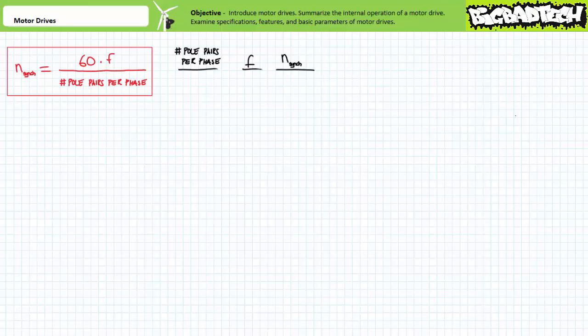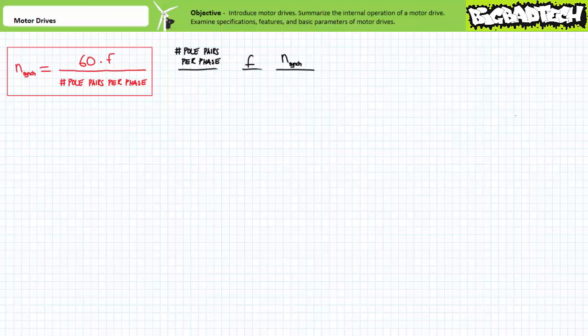Regardless of the terminology employed, all of these devices are solid-state power electronics devices that vary or adjust the magnitude and frequency of applied voltage to a motor under their direction. Returning to those qualities that affect synchronous speed — notably frequency and number of pole pairs per phase — you can see the clear advantage of a motor operated with a motor drive. Given frequency is no longer fixed but rather a continuously variable quantity, the synchronous speed can now be continuously varied for a mechanically simple motor with a fixed number of pole pairs per phase.